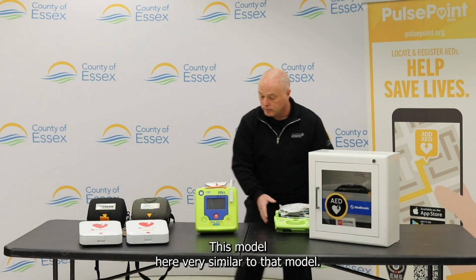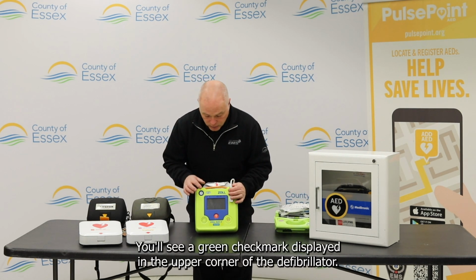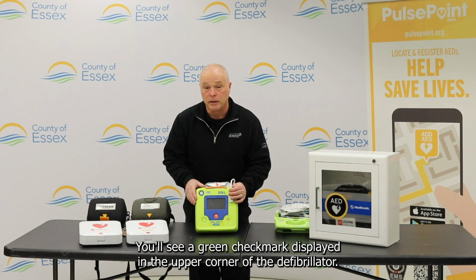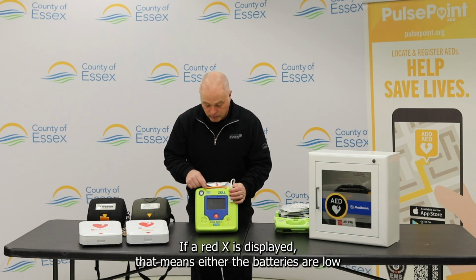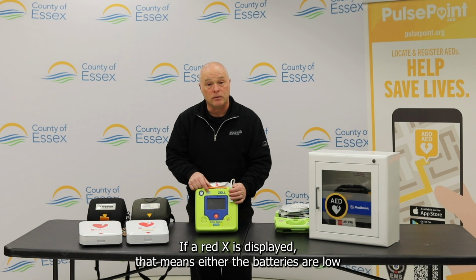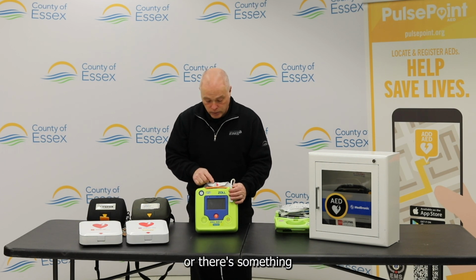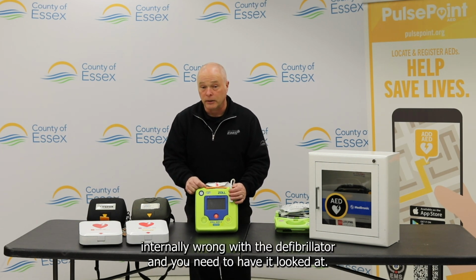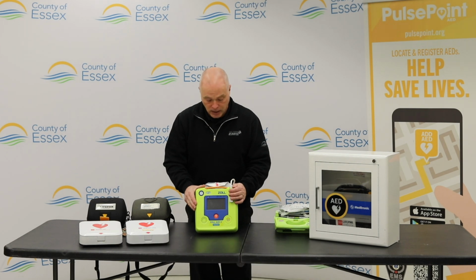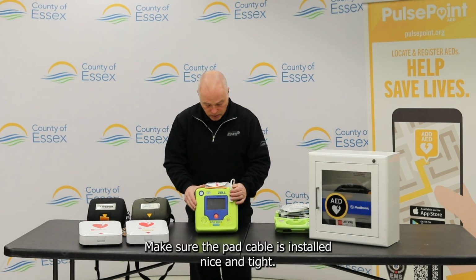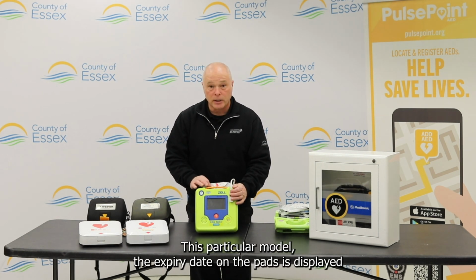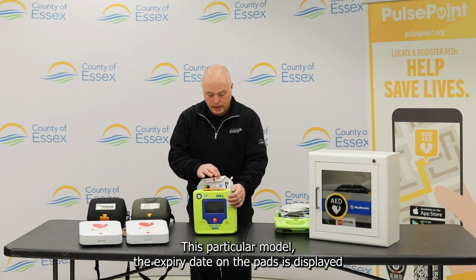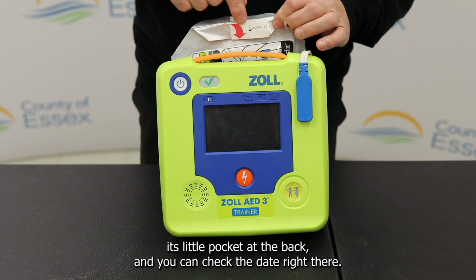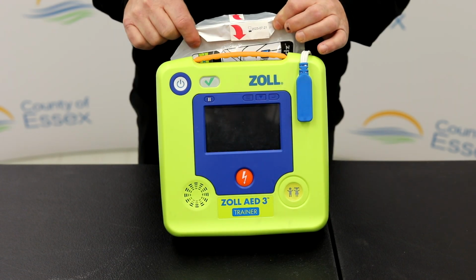This model here, very similar to that model, you'll see a green check mark displayed in the upper corner of the defibrillator. If a red X is displayed, that means either the batteries are low or there's something internally wrong with the defibrillator and you need to have it looked at. Make sure the pad cable is installed nice and tight. This particular model, the expiry date on the pads is displayed right here when it sits in its little pocket at the back, and you can check the date right there. That's all you need to do to check this defibrillator.